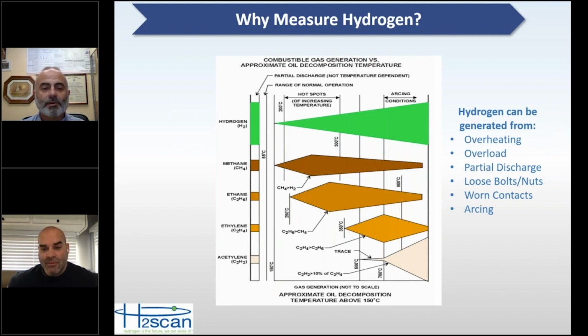If you have large power transformers, you know that without any external cooling, you might have a 50 MVA transformer, but add a couple of good stages of cooling, and now that 50 MVA transformer is good for 100 MVA. And so if that cooling's not working and you're loading your transformer up to 100 MVA, you're certainly going to be generating hydrogen and probably some of these other gases. And so again, hydrogen can alert you to a lot of different things going on in your transformers.